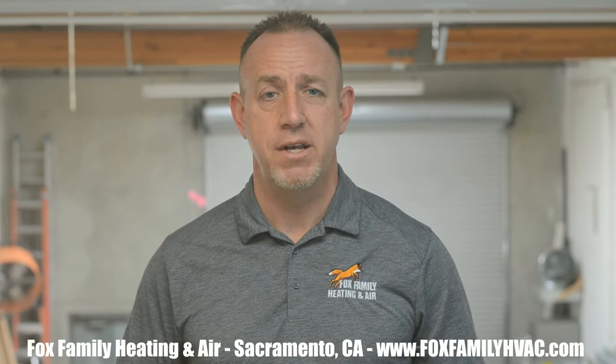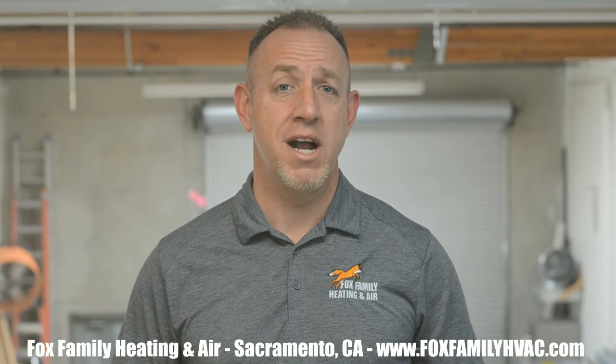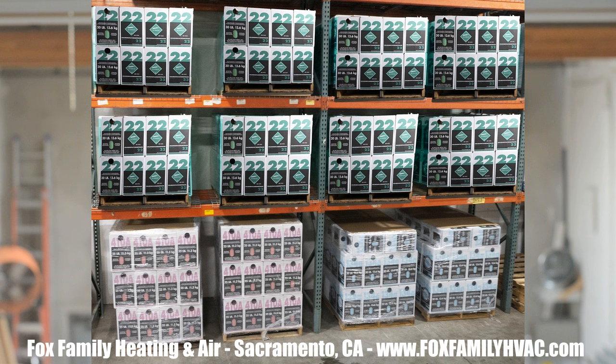Will R22 and R410A still be available to service existing HVAC equipment? Absolutely. But some HVAC companies will still use this as an opportunity to convince unsuspecting customers that R22 and R410A systems are illegal to use now, and that they can't repair their existing system. It's a regular tactic I hear all the time — and shame on those technicians that do that; you're what gives this industry a bad reputation. Warehouses will be full of perfectly legal R22 and alternative replacements until at least 2030, and R410A will be available for much longer than that. The protocols in effect are there to phase out the production of new, virgin refrigerant — recycled refrigerants and current inventory will be around much longer after they stop making it.